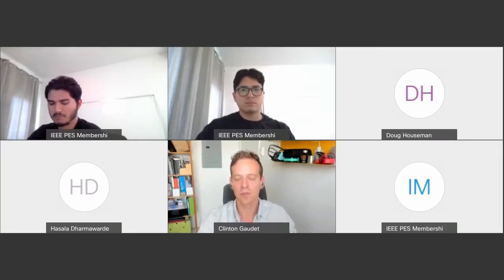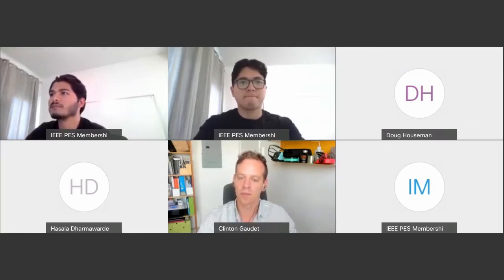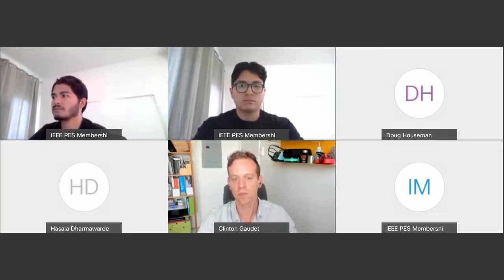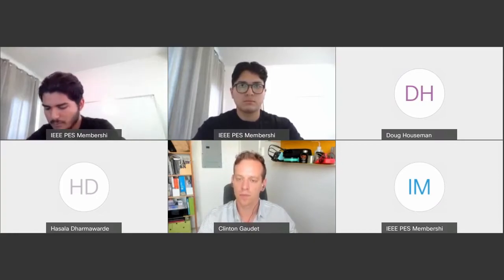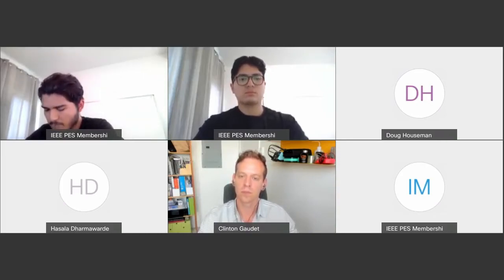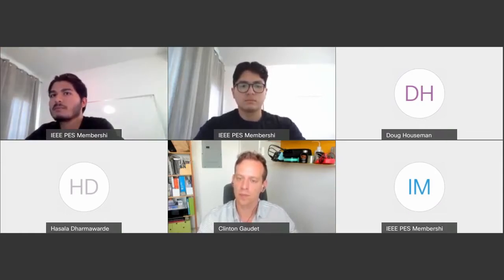Absolutely. If you can put a cap bank below a line and far enough away that you don't have to worry about any interference, and you've got enough room between the communication zone and the hot zone, that cap bank, when it's disconnected from the grid, can be worked by almost anybody. So if what you need to do is go change a relay or a timer or a radio, then somebody who's not qualified as a lineman can go do that work. That's a big difference in cost, and a big difference in the setup and teardown time at the location and the permissions required to do that work.